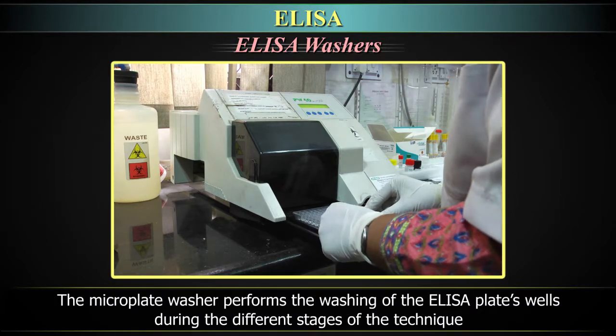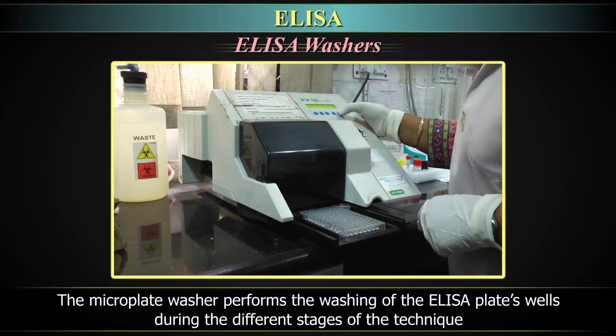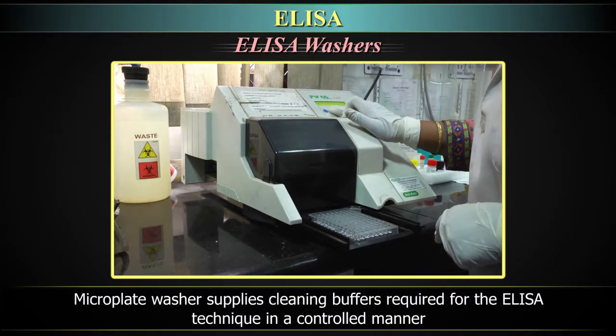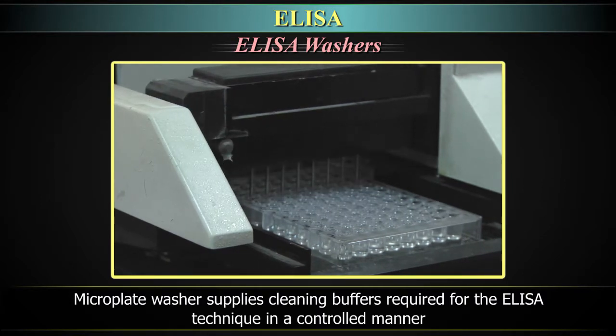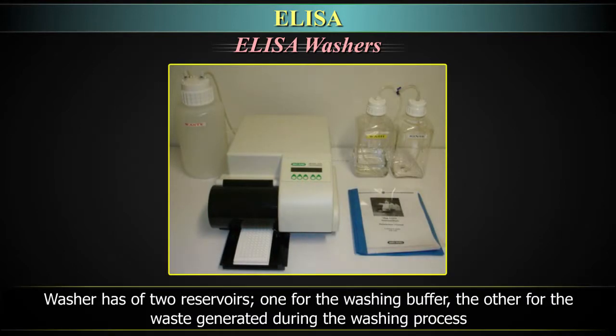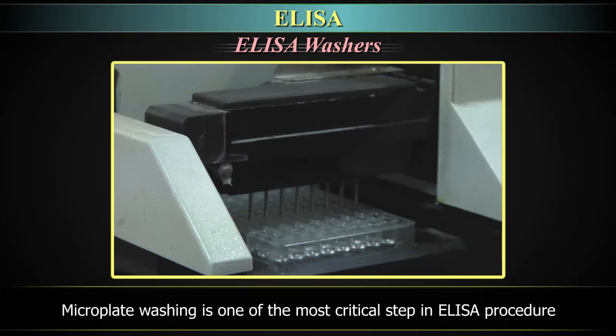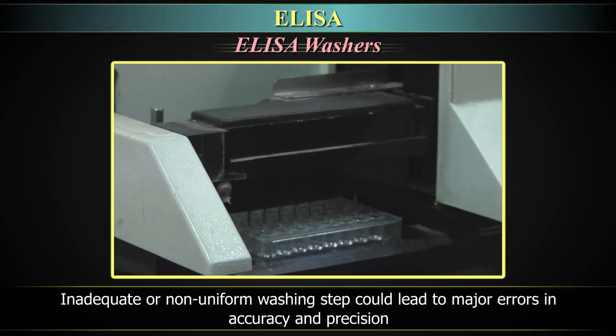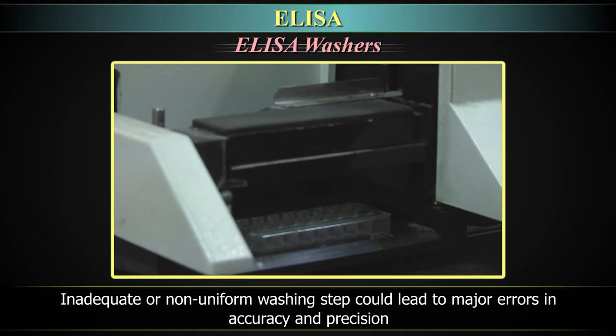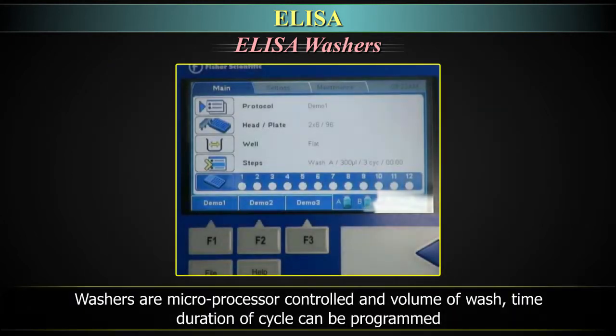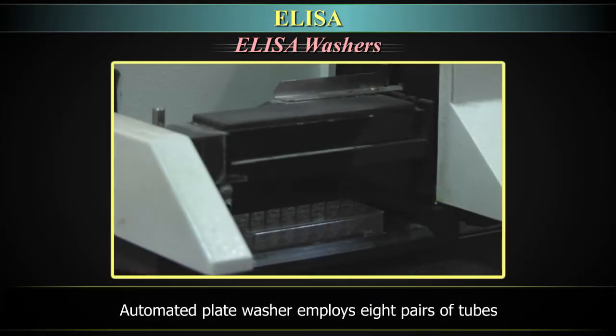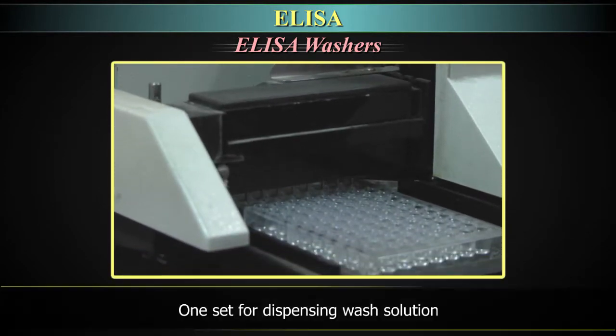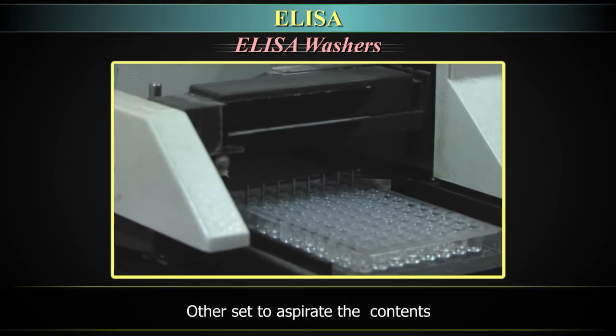The microplate washer performs the washing of the ELISA plate wells during the different stages of the technique. It supplies cleaning buffers required for the ELISA technique in a controlled manner. The washer has two reservoirs: one for the washing buffer, the other for the waste generated during the washing process. Microplate washing is one of the most critical steps in the ELISA procedure. Inadequate or non-uniform washing could lead to major errors in accuracy and precision. The washers are microprocessor controlled and volume of wash and time duration of cycle can be programmed. Automated plate washer employs eight pairs of tubes: one set for dispensing wash solution, the other set to aspirate the contents.